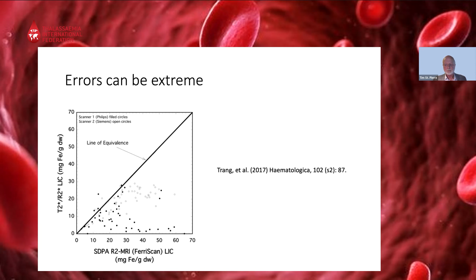And we expect, in the best case scenario, the data points to be scattered around that black line. But in the case of the Philips scanner, for example, we see that down at the low levels, there's a little bit of correspondence between the two measurements. But as we go to high liver iron concentrations, we get extremely severe errors. So for example, let's take this patient here. With FerriScan, the liver iron concentration was extremely high at 50 milligrams of iron per gram dry tissue, whereas the T2 star method gave a value of around about 3 or 4 milligrams of iron per gram dry tissue.